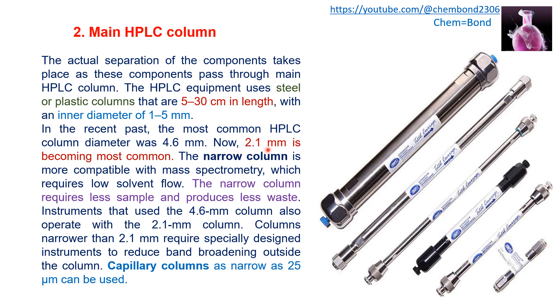Older instruments operated with 4.6 mm columns can also be operated with 2.1 mm columns. Columns narrower than 2.1 mm require specially designed instruments to reduce band broadening outside the column, while the 2.1 mm column fits into instruments designed for 4.6 mm. Capillary columns narrower than 2.1 mm — as narrow as 25 micrometers — can also be used.